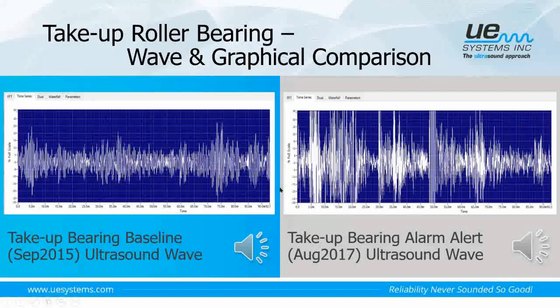Although this is not a good noise quality for normal bearings, we can't just replace every bearing. A bearing is a mechanical component. It will fail over time. So by condition-based monitoring, we can monitor these bearing conditions. And this bearing gave way after 2 years with a very rough noise quality.